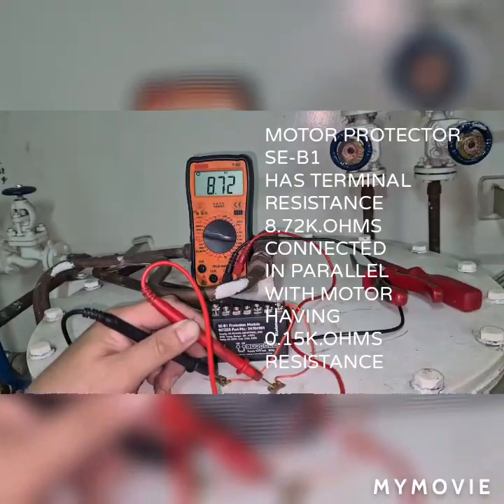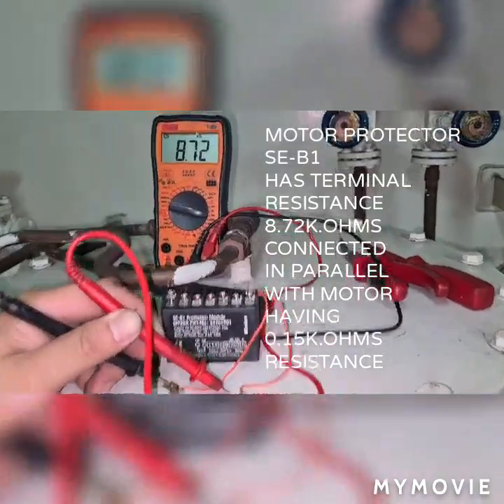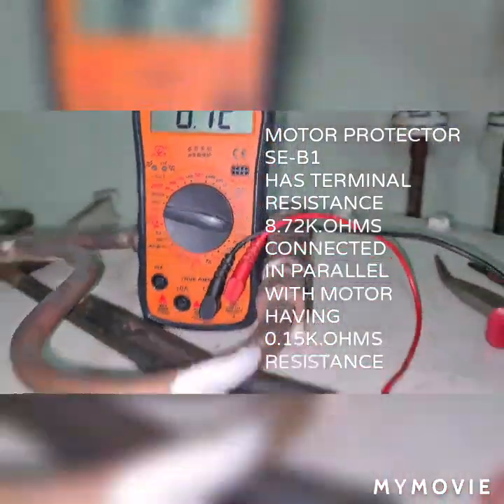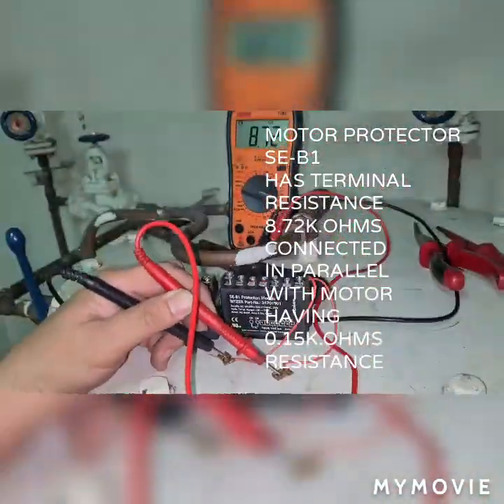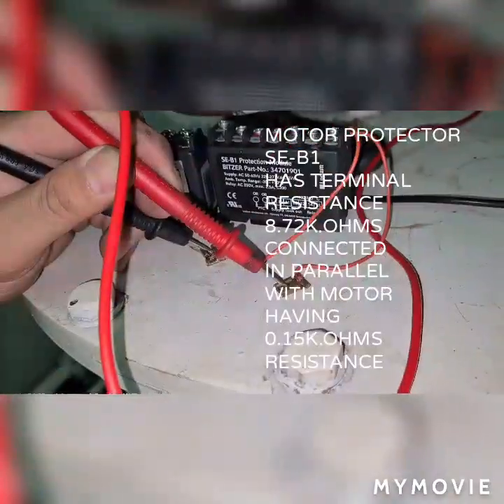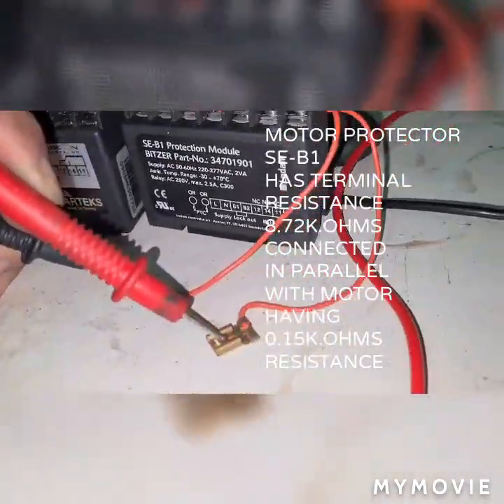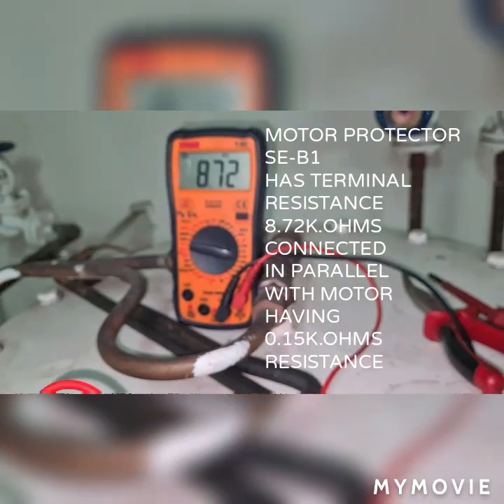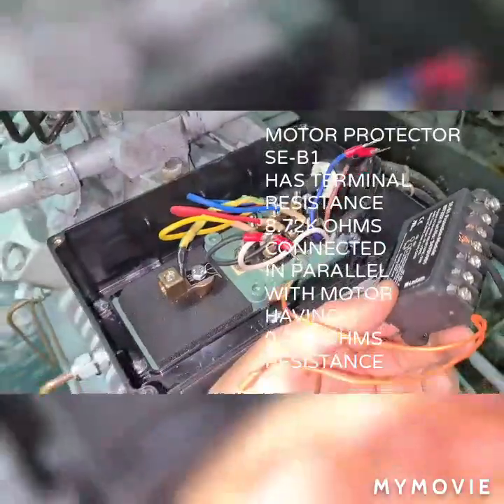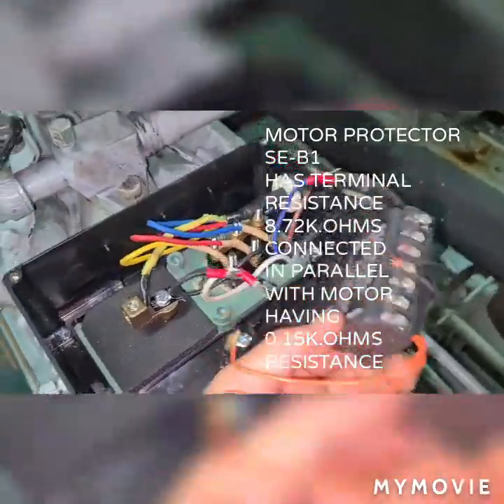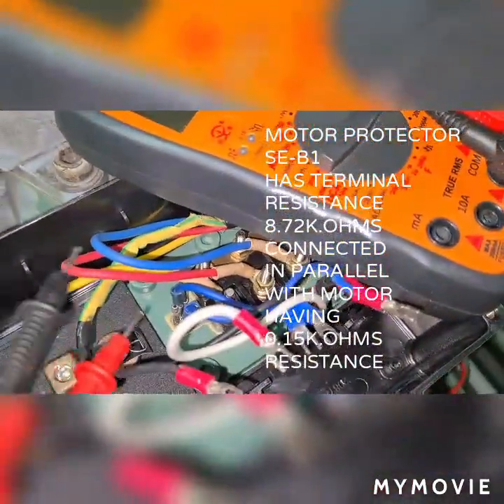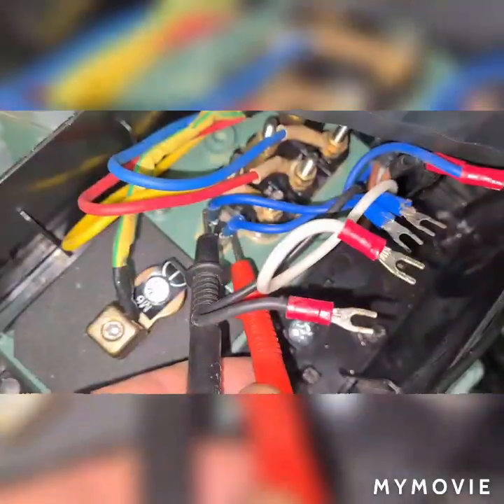Here, as you can see, I measure the terminal orange cable having 8.72 kilo ohms, and this 8.72 kilo ohms is connected in parallel with the PTC connected on my motor. The PTC resistance I measure here having 0.15 kilo ohm. So by connecting 8.72 kilo ohm with 0.15 kilo ohms PTC sensor on your motor, you may expect that the resistance will be lowered. So take note, this PTC having 0.15 kilo ohms which was connected on my motor.